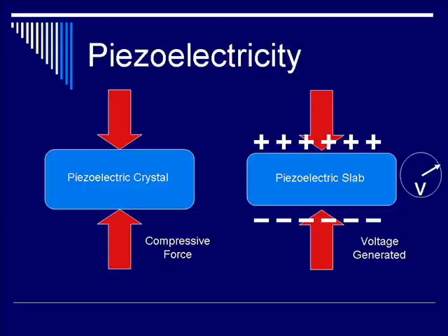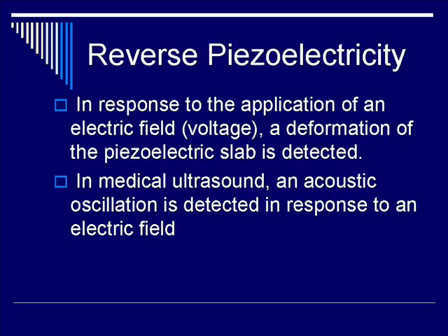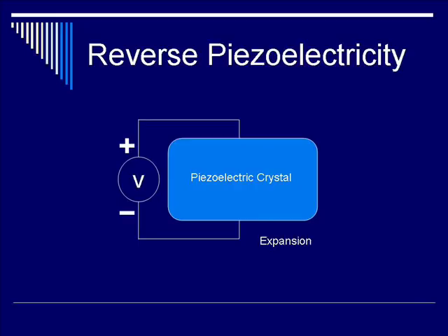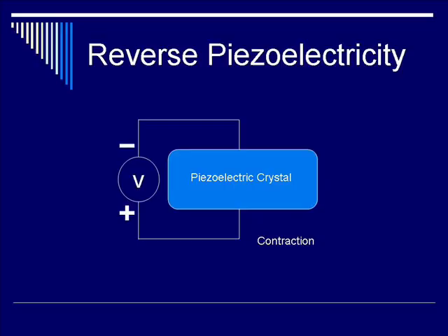What is reverse piezoelectricity? It is just the opposite of piezoelectricity. In this case, you apply an electric voltage across the piezoelectric crystal and you get a deformation of the slab. In medical ultrasound, an acoustic oscillation in the form of an ultrasound wave is formed in response to the electric field. By hooking up the voltage source in one orientation, you achieve expansion of the crystal; if you flip the voltage leads — negative on top and positive below — you experience a contraction or shrinkage of the piezoelectric crystal.